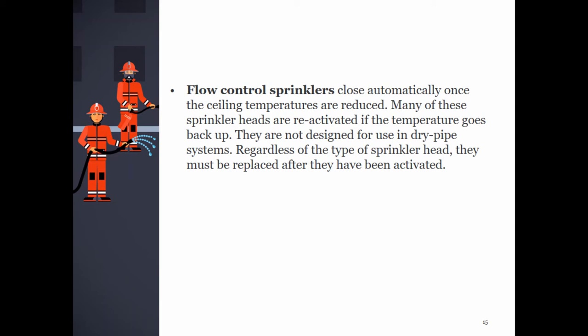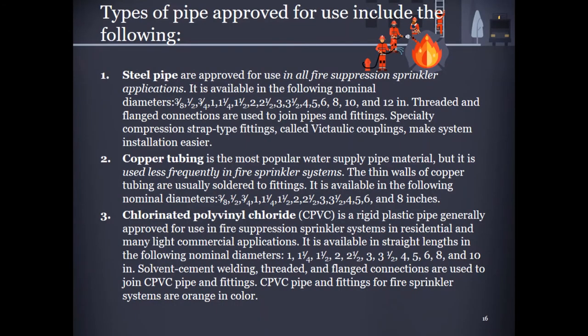Sprinkler heads must be replaced after they have been activated. Types of pipe approved for use include: Steel pipe — approved for all fire suppression sprinkler applications; threaded and flanged connections join pipes and fittings, and specialty victaulic couplings make installation easier. Copper tubing — the most popular water supply pipe material but used less frequently in fire sprinkler systems; thin walls are usually soldered to fittings. Chlorinated polyvinyl chloride (CPVC) — a rigid plastic pipe generally approved for residential and many light commercial applications; solvent cement welding, threaded, and flanged connections are used. CPVC pipe and fittings for fire sprinkler systems are orange in color.